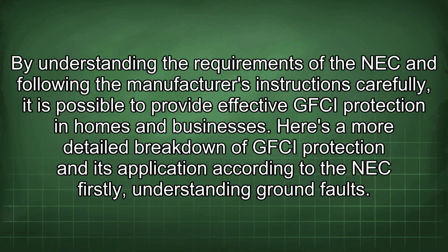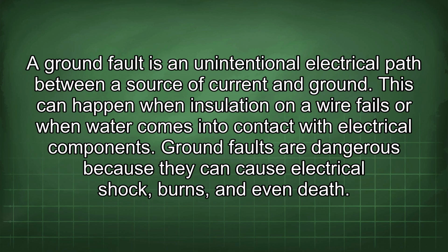Firstly, understanding ground faults. A ground fault is an unintentional electrical path between a source of current and ground. This can happen when insulation on a wire fails or when water comes into contact with electrical components. Ground faults are dangerous because they can cause electrical shock, burns, and even death.